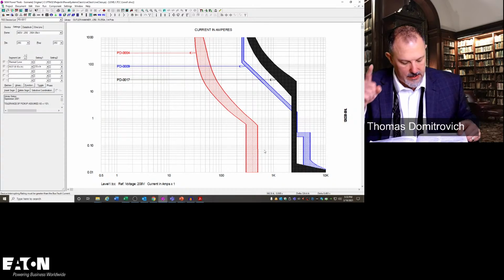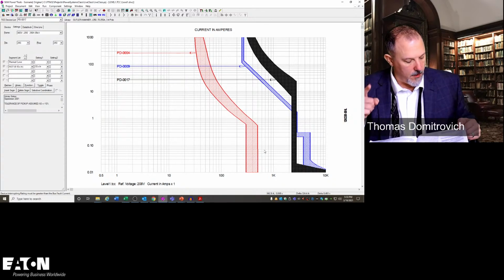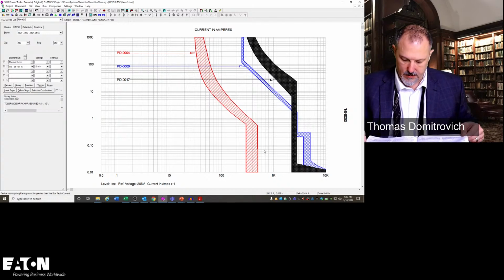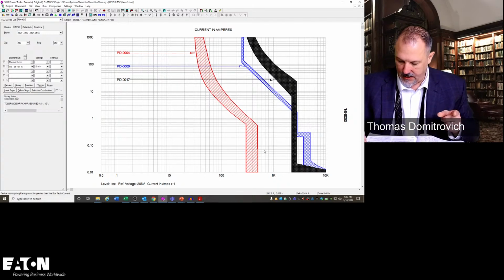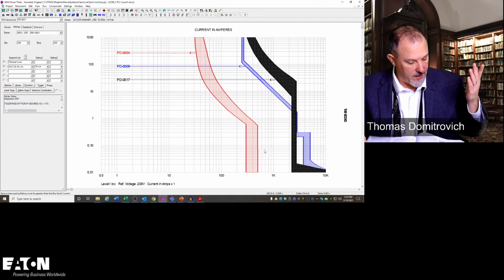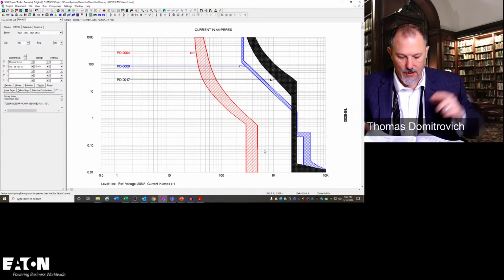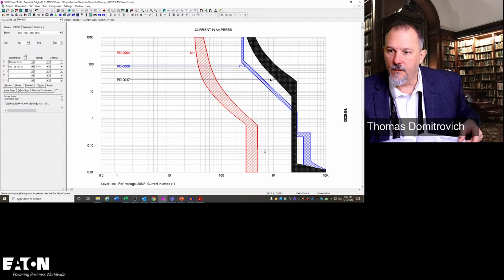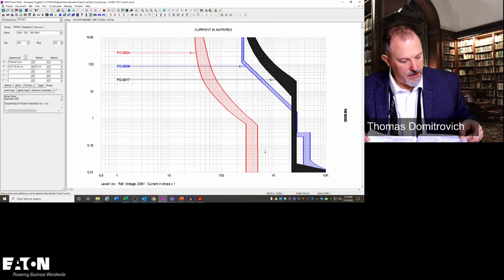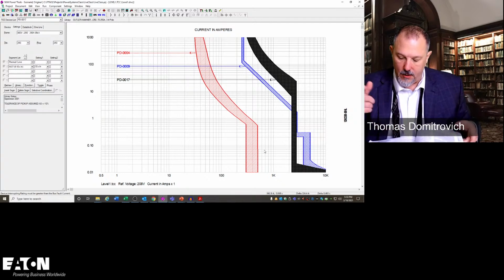So now we're going to learn what the tables are. But what am I checking the tables for? I thought it was 517.17, but it's not. 517, I'm looking for coordination. Oh my goodness, I should know this off the top of my head. There it is. No, that's ground fault. It's ground fault. For full selectivity. That's right, I'm looking for full selectivity. For what though? But I need to compare something. When I go to the tables, I need one important data point. What is it that I need in that data point?